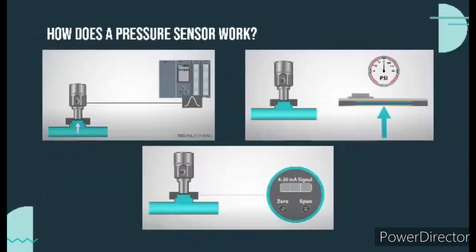How does a pressure sensor work? So, in a nutshell, it converts the pressure to a small electrical signal that is transmitted and displayed. These are also commonly called pressure transmitters. Because of this, two common signals that are used are a 4 to 20 milliamp signal and a 0 to 5 volt signal.